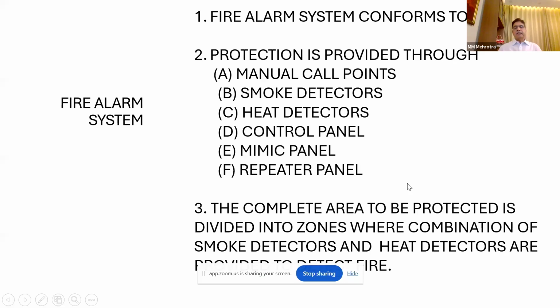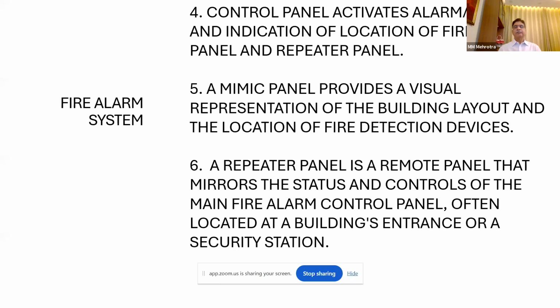Now, this is how detectors are provided. Detectors are provided like we do internal electrification. We find out how many lights and fans are required in a room. Same way, the complete area is divided into zones where, depending upon the capacity of detector, number of detectors will come. Each detector has a supply coming to my control panel. Control panel, mimic panel, repeater panel, I have already told. So mimic panel is giving visual representation of the building layout and location of the fire detection devices. So my LED will tell me where the fault is.